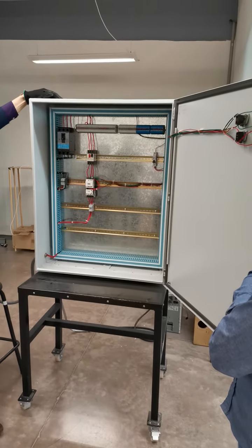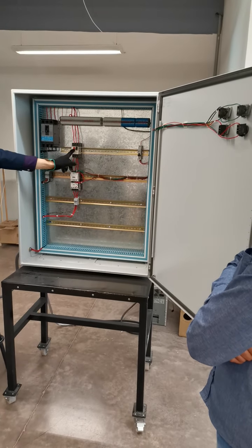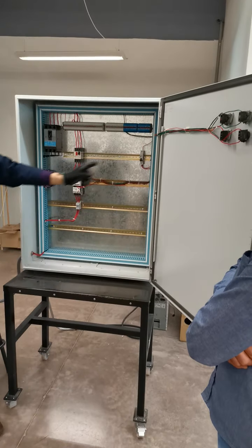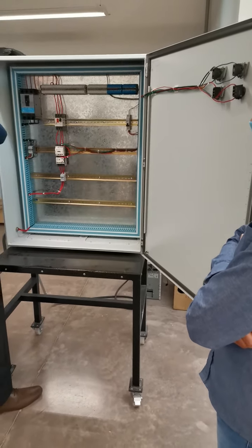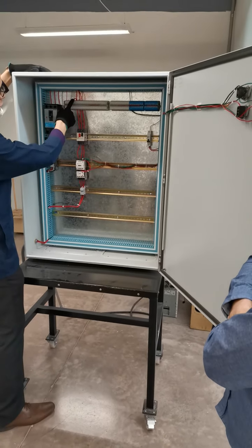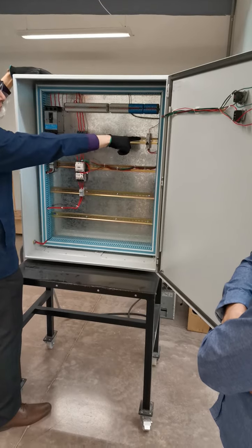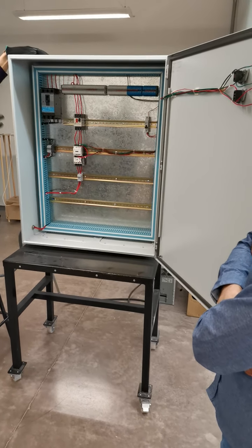You cannot have the same disconnector for power and control. You need to have one for power, this one, and one for control, that is this one over here. So, from one of the lines, you can select the one that you want. If you check over here, we have the reach, and then this one is coming over here for this one. It is indifferent if you select line 1, 2, or 3.